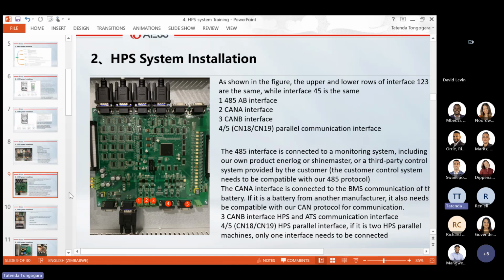Okay, so inside the HPS, we have 3 main boards: the control board, the relay board, and the sampling board. The control board is where you load your program and connect your RS-485 connections, CAN A, CAN B. On point 1, this is our RS-485 port, where you connect your Enerlog, your Shine Master, all the monitoring.